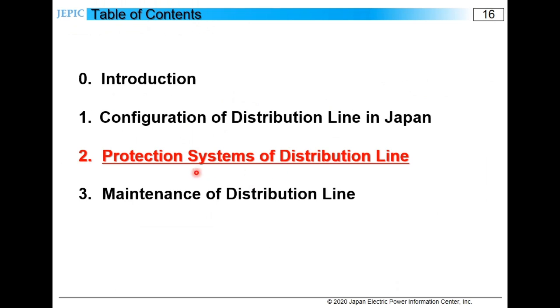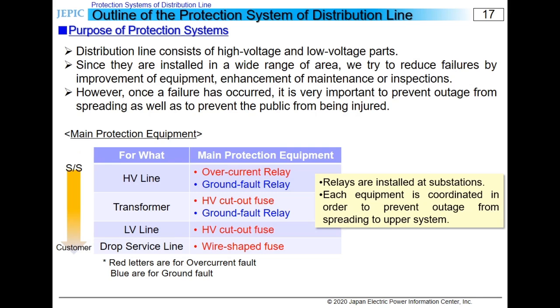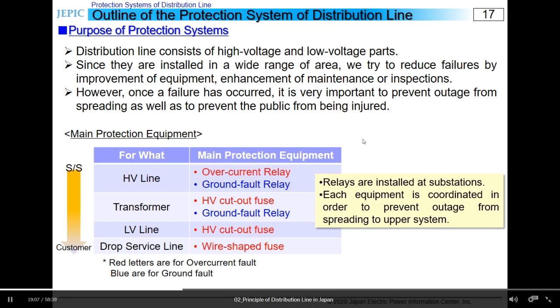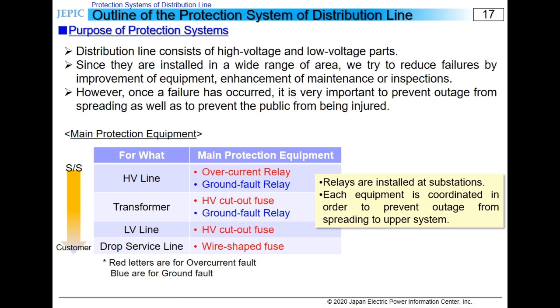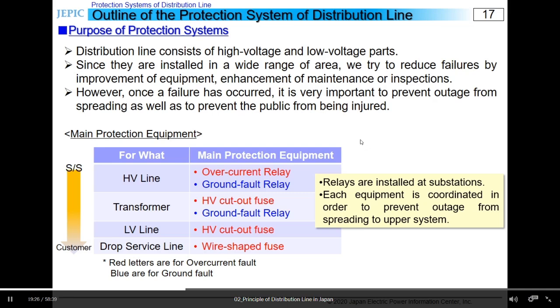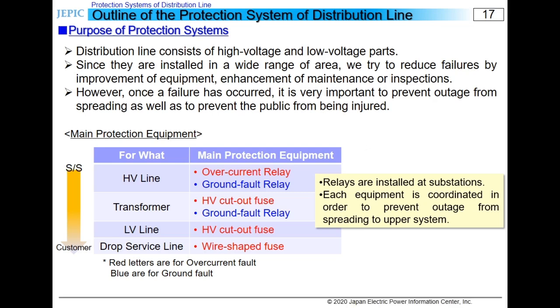Next chapter is about protection systems of distribution line. Distribution line consists of high voltage and low voltage parts. Since they are installed in a wide area compared with other electric power facilities, we try to reduce failures by improvement of equipment and enhancement of maintenance and inspections. However, once a failure has occurred, it is very important to prevent outage from spreading as well as to prevent the public from being injured.